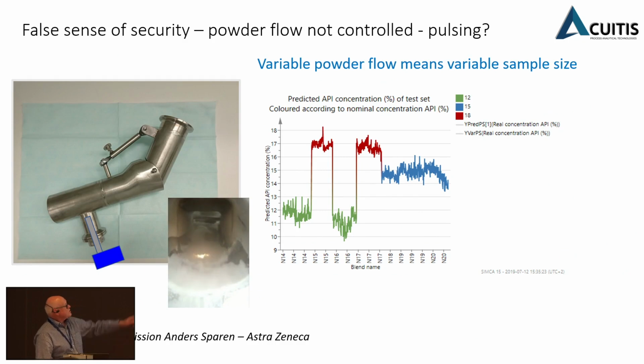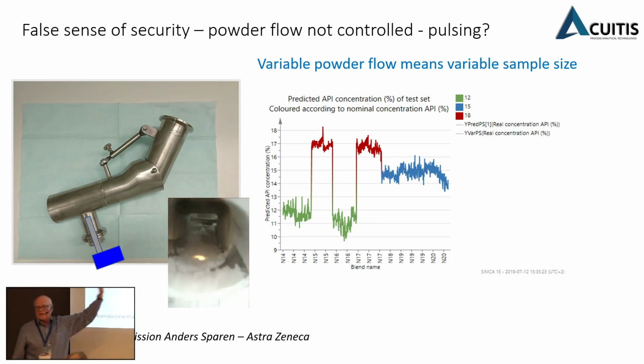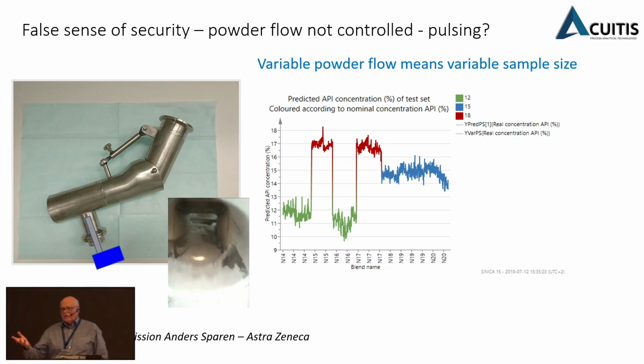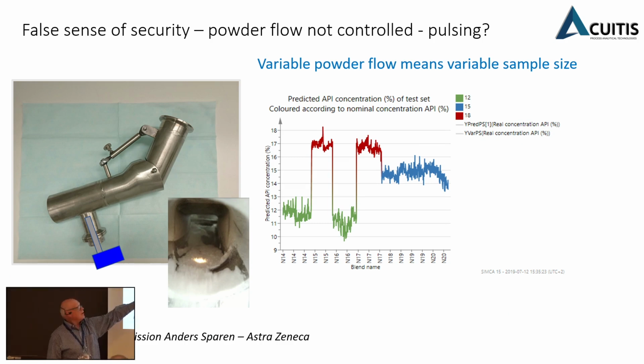And the worst one of those is these gravity-fed chutes like this. And you can see in here, every now and again there's a flash of light, and that's because the flow of the powder dips enough that the light gets through. So those sorts of chutes are a very poor environment to put a Sentronic FO probe. And unfortunately, a number of companies that sell continuous manufacturing equipment have a prevalence for selling these chutes. In fact, some spectrometer companies have been known to do that as well.